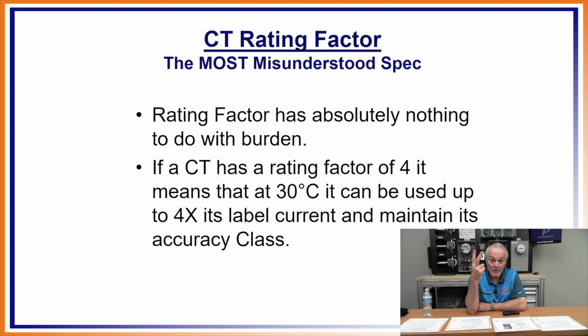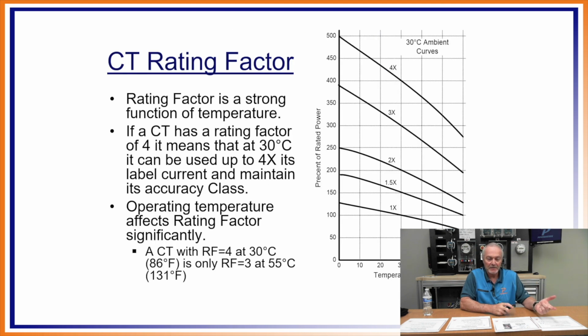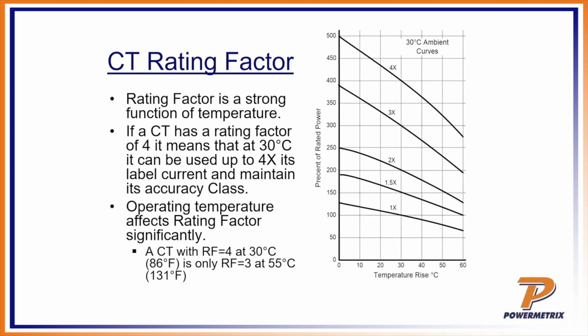What did we just say? The two things, burden and temperature. And the temperature directly affects the rating factor, okay? And you can see right here, as I increase my temperature at the bottom, I start getting a derating of that rating factor. When I get over here, in like 30 degrees C, yeah, that looks good up there. I got 4 times. If I get out to 60, look where that 4 times has dropped. It's dropped all the way down to between 250 and 300.